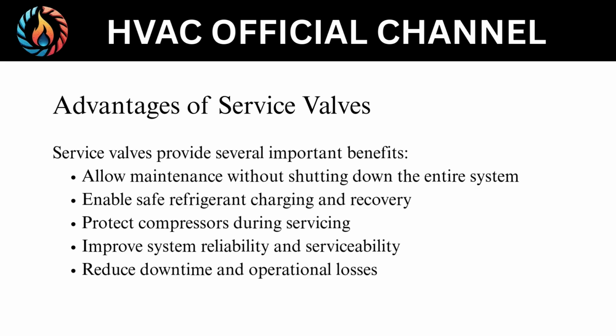Advantages of service valves. Service valves provide several important benefits. Allow maintenance without shutting down the entire system. Enable safe refrigerant charging and recovery. Protect compressors during servicing. Improve system reliability and serviceability. Reduce downtime and operational losses.